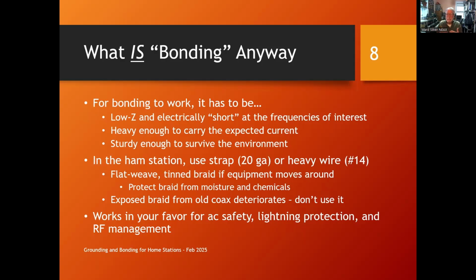If it's a lightning protection conductor and you expect lightning surges to go through it, it's got to be heavy enough to handle that. You're talking about kiloamps, which makes a circuits guy like me really nervous. A small wire hit with a kiloamp, poof, it makes a nice green lightning bolt for a second, and then it's gone. So this is why your building codes say number 6, number 2, number 4, whatever.